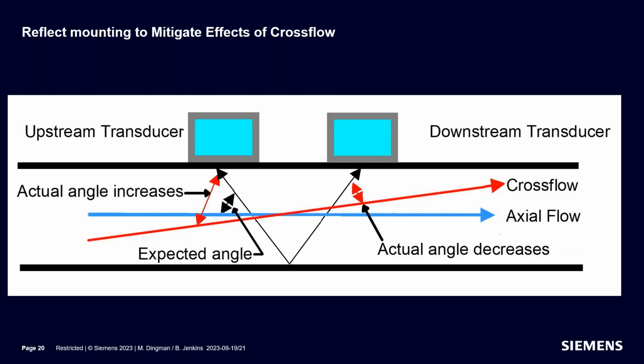So the speed of sound of the fluid is still the same. So the meter is still calculating the same beam angle relative to the flow, which means it's wrong. So you could see what the expected angle is and what the meter is computing, but you could see what the actual angle is on the left, and that's going to produce an error, and an error of sizable proportions. And if you were in direct mount, you would be in a big error condition because there's no way of knowing otherwise that you're seeing a crossflow condition.